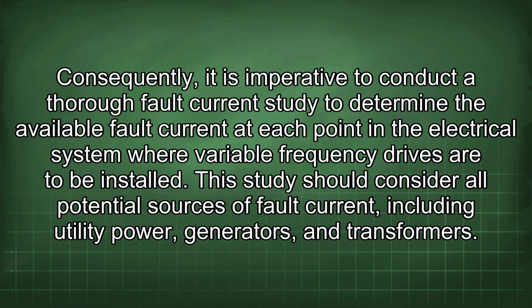Consequently, it is imperative to conduct a thorough fault current study to determine the available fault current at each point in the electrical system where variable frequency drives are to be installed.